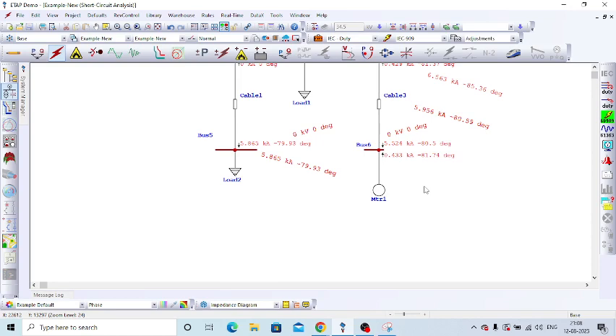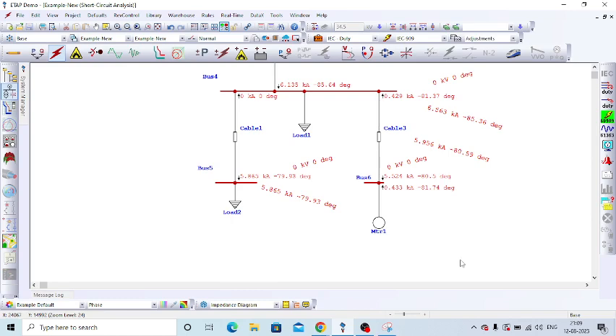So that's what I explained in the last session. In conventional electrical machines, including generators and motors, having inertia, at the time of fault they will contribute some amount of fault current to the fault point. But in modern inverter based systems, like a solar plant or wind plant, those elements don't have a rotating part, that is inertia. So if any fault happens, those elements will not contribute any fault current to the faulted point. I hope everyone is clear with that. If you have any doubt, you can please turn on your mic and ask me some questions. Okay, if there is no question, then I will continue further.